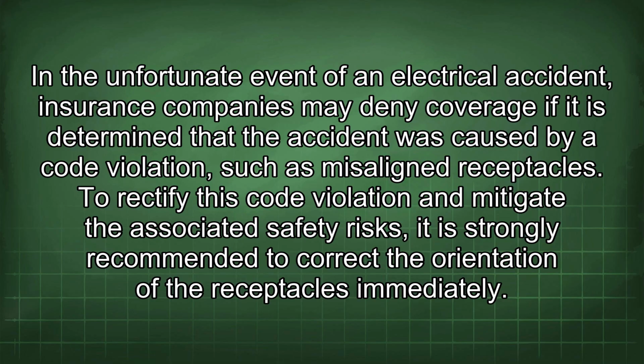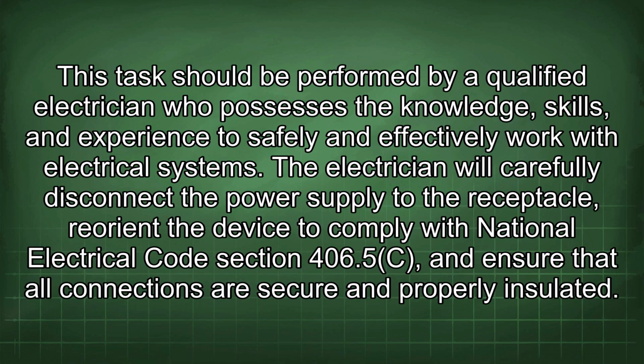To rectify this code violation and mitigate the associated safety risks, it is strongly recommended to correct the orientation of the receptacles immediately. This task should be performed by a qualified electrician who possesses the knowledge, skills, and experience to safely and effectively work with electrical systems. The electrician will carefully disconnect the power supply to the receptacle, reorient the device to comply with National Electrical Code Section 406.5c, and ensure that all connections are secure and properly insulated.